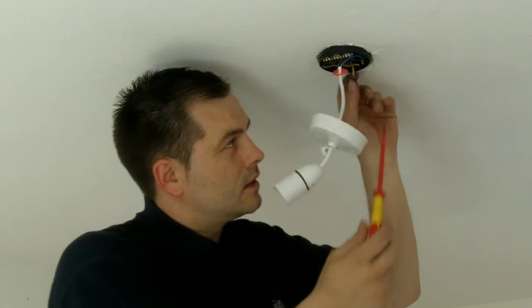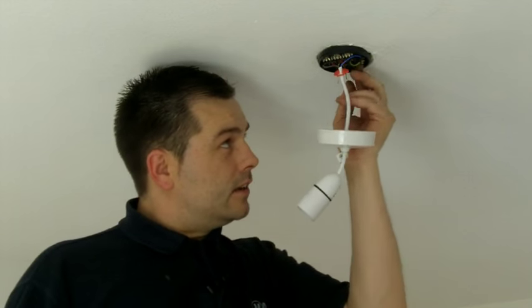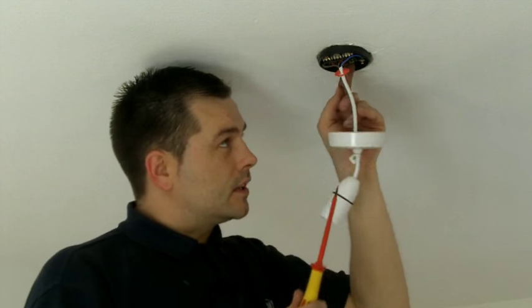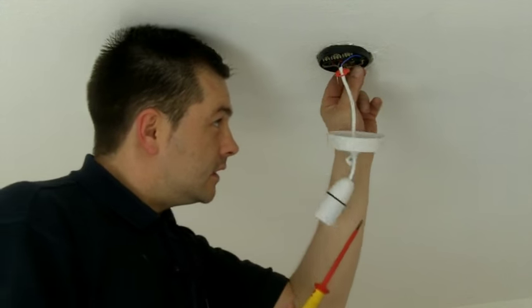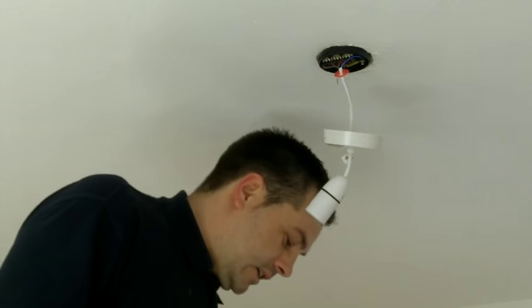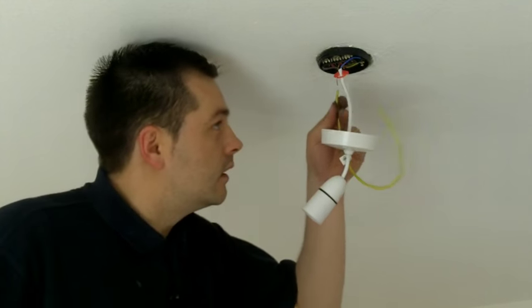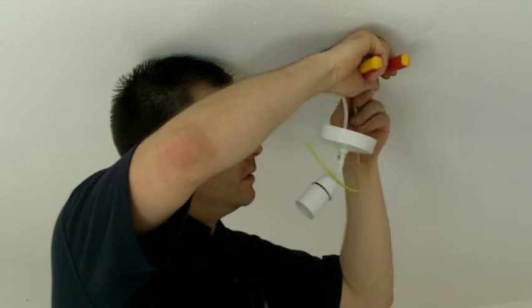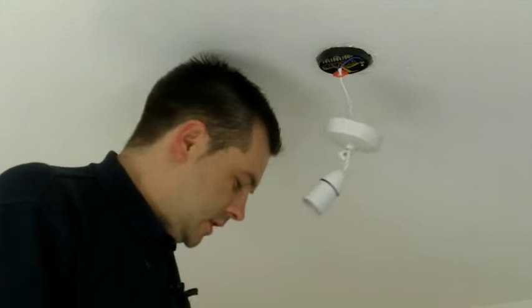Now, the very last to connect in this instance is the earth cable. And this is actually one of the most important cables in the light fitting. It means that in the event of an electrical fault, your electricity will disconnect, only if the earth cable is connected. So please ensure that the earth cable is actually sleeved with a green and yellow sleeving. And this is number one to identify the earth cable, and number two to also protect it from making contact with either the red or the black cables in the light fitting.